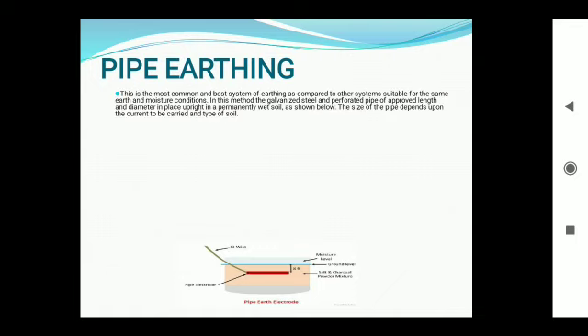Now the second one is the pipe earthing. You can see the image of a pipe earthing. There is a salt and charcoal powder mixture under the ground level, and a pipe electrode is connected with the GI wire. This is the most common and best system of earthing as compared to other systems suitable for the same earth and moisture conditions. In this method, the galvanized steel and perforated pipe of approved length and diameter is placed upright in a permanently wet soil, as shown below.